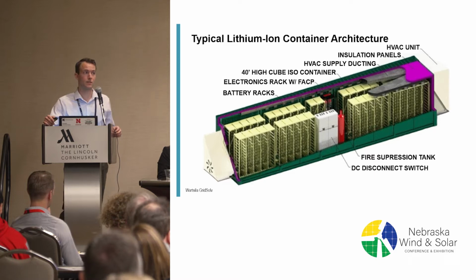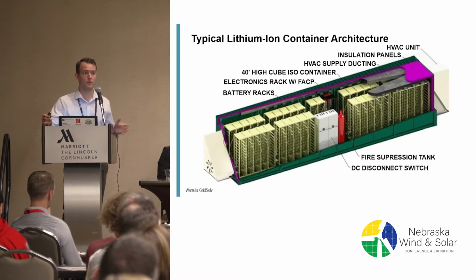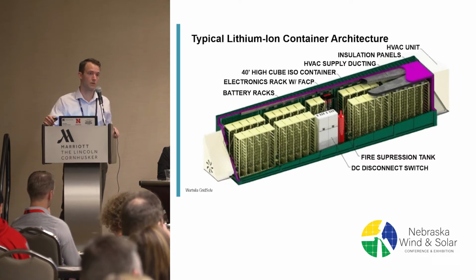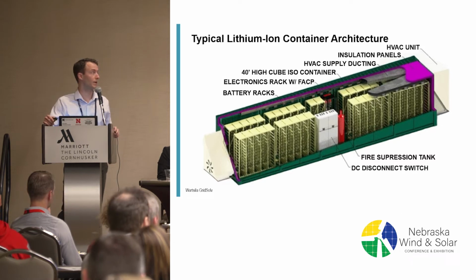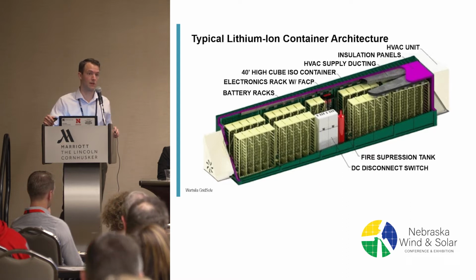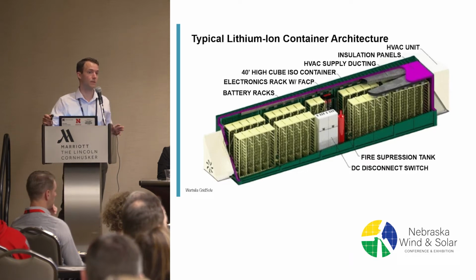About 5 years ago, these were primarily the ISO container, the steel box, 40 or 53 foot ISO box, retrofitted with racks of battery modules, which were packages of battery cells. Those are all wired together in series and parallel onto one DC bus within the container, and in most cases that container has a single DC output. There are some OEMs integrating the inverter or power conversion system within the container, in which case you have an AC output, but still most OEMs and most products now are a DC configuration.